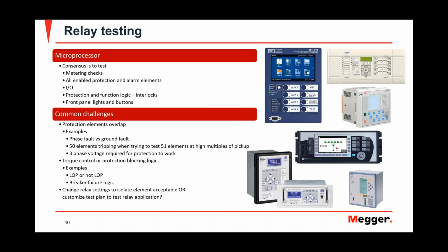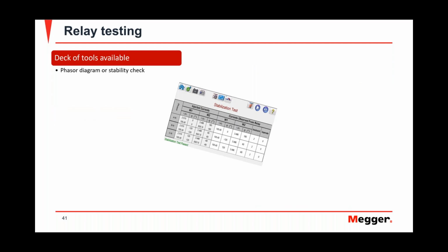So the big question with microprocessor relays: do you change the relay settings in order to test that element? Are you driving just for a test result, or are you driving to test the application? My advice is try to test the relay application, understand the application, and come up with a test from that, not just isolate the protection. When you test like that, you're more able to really understand the intent of the protection, instead of just driving for a result. I know it's easier said than done, and it probably takes practice, but it's something that you should create a habit of.